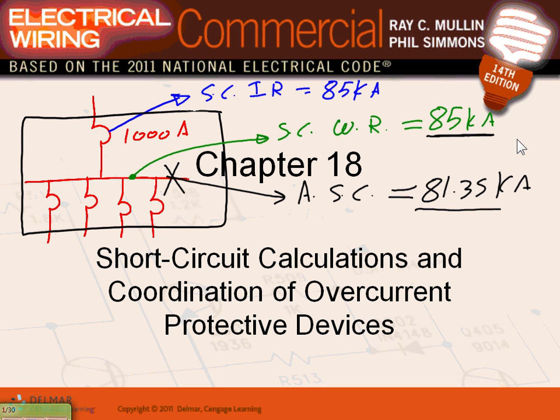Withstand rating of equipment, guys, UL will take the switchgear and literally, physically, mechanically pump 85,000 amp into the switchgear and watch what's going to happen to it. If it's still there for a certain amount of time, of course, not forever, say 3 cycles, most equipment is 3 cycle rated. 3 cycles, 3/60, 1/20th of a second. For 1/20th of a second, that switchgear should be intact. If it's ANSI switchgear, you're talking about 30 cycles, half a second. For half a second, this switchgear should be intact when you pump that amount of current inside it.